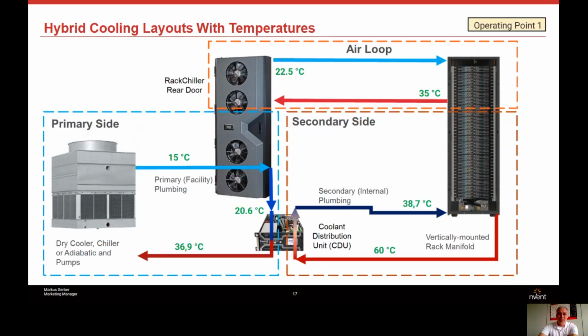If not, what we did is we just put in some examples. So operational point 1: 15 degrees Celsius on the facility side on the water circuit. We say we want to get 22.5 degrees Celsius on the air side, with a 35 air side return temperature. And then we support the liquid to liquid heat exchanger in the CDU. And we get the return temperature to the facility of 36.9 degrees. Makes sense so far? I would say yes.